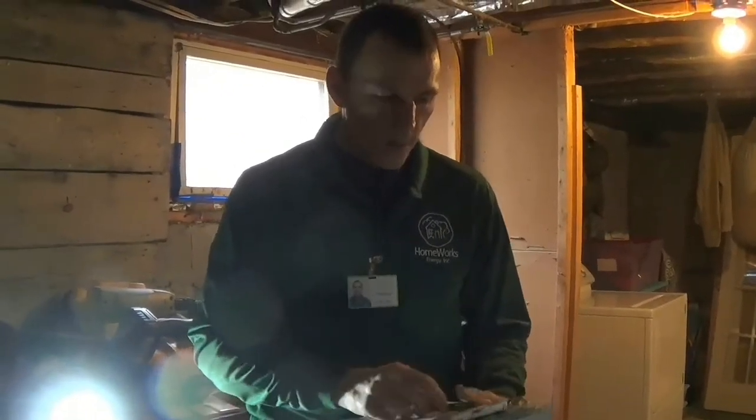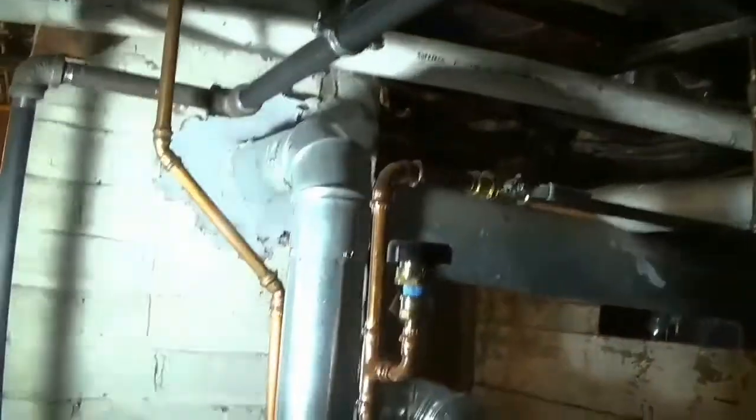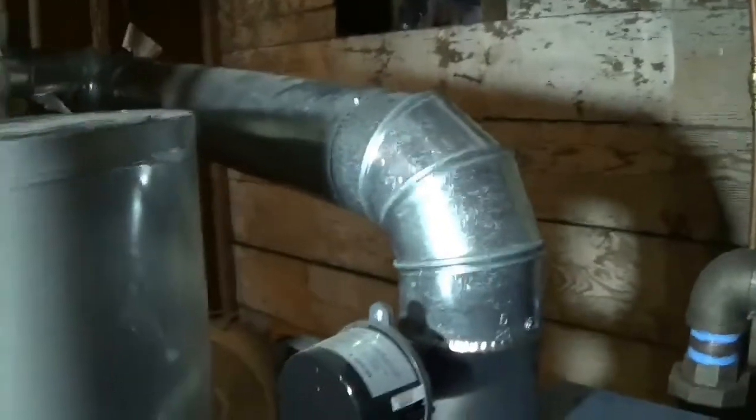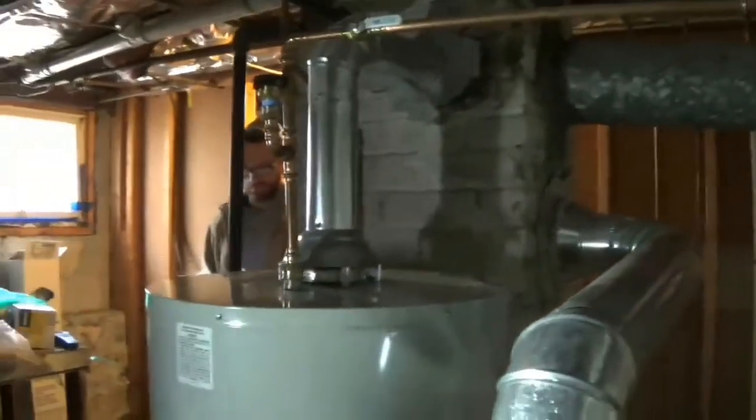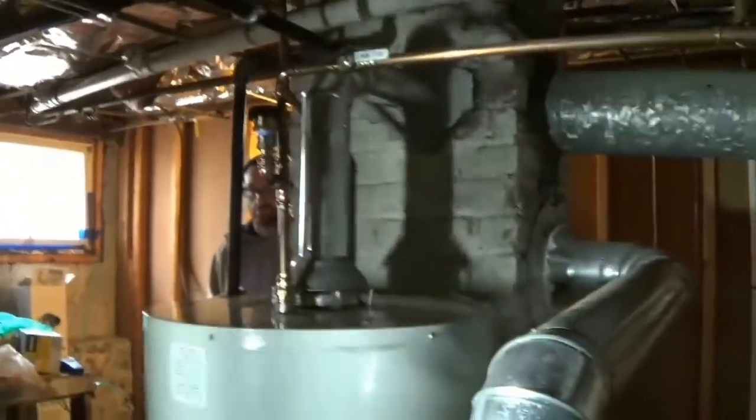Are there any broken, corroded, or detached vent pipes? I've looked at these vent pipes. This is what we're talking about when we say vent pipes, the metal connections between the combustion appliances and the masonry chimney. These are called vent pipes or flue connectors, and they're in perfect condition. There's no corrosion on the vents. I don't see any corrosion on any of the water pipe connections anywhere. This equipment looks like it's in pretty decent shape.